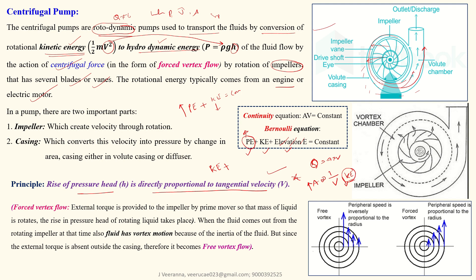This process uses the forced vortex and free vortex concepts. In a forced vortex, the impeller rotates due to an external torque from the prime mover. The liquid on the impeller also rotates, gaining velocity, which results in a rise in pressure head of the rotating liquid — this is called the forced vortex.